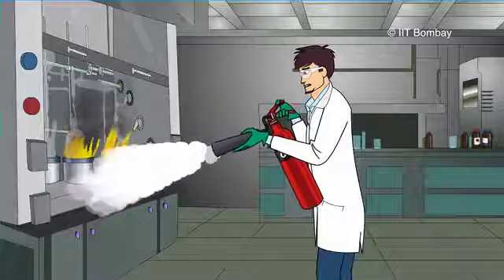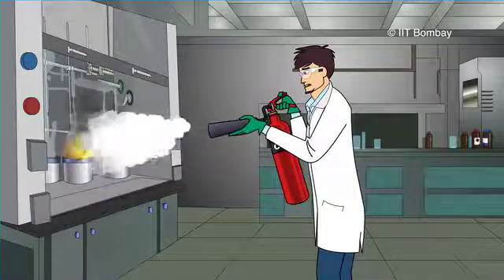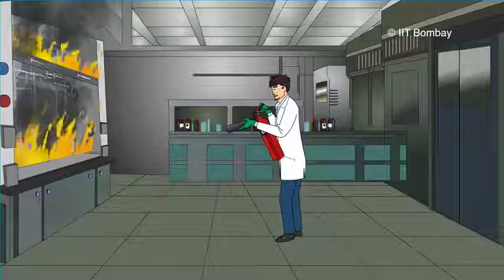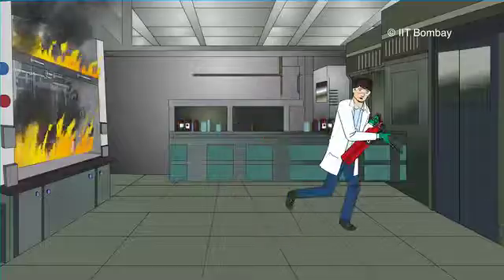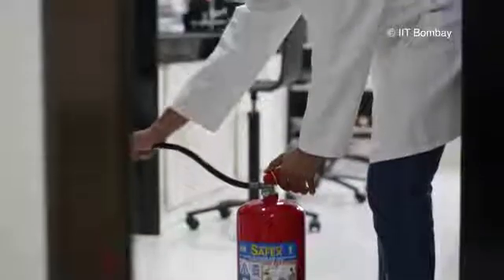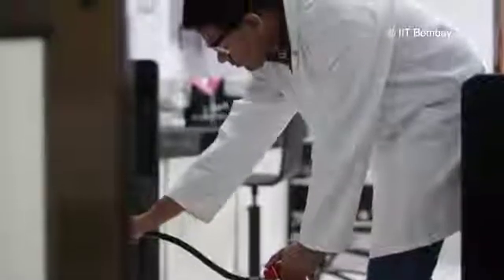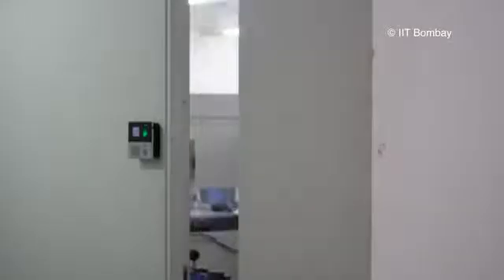Fight a fire only if it is localized and small. Evacuate the area if the fire has spread or if you find that the room is filled with smoke. While fighting a fire, make sure that there is an exit behind you so that you can escape if the fire spreads fast. While you evacuate the room, close the door behind you — this confines the spread of fire and smoke. Make sure that you do not lock it.